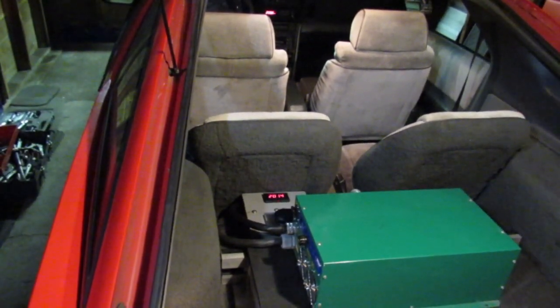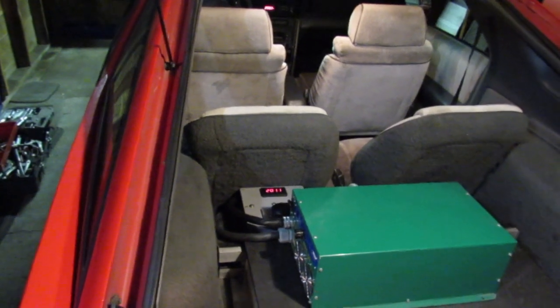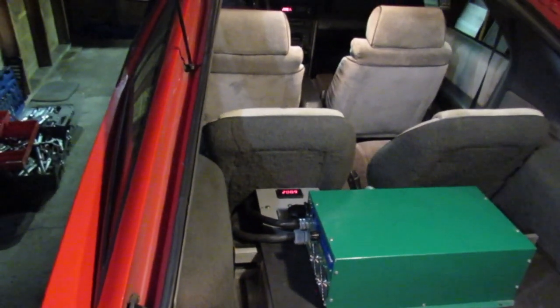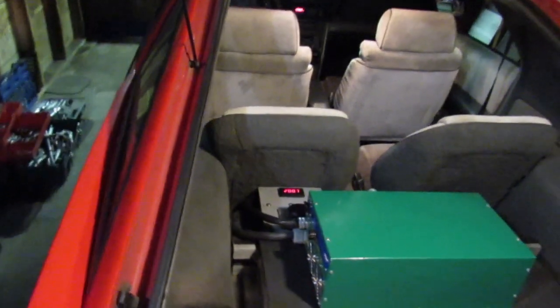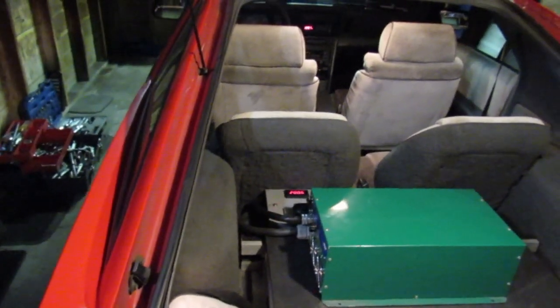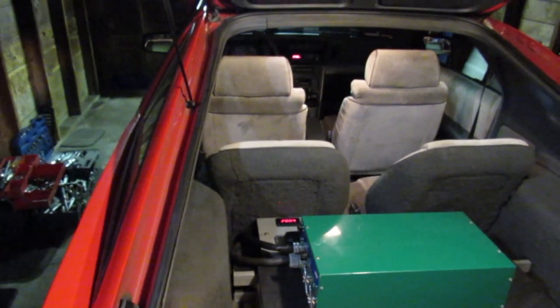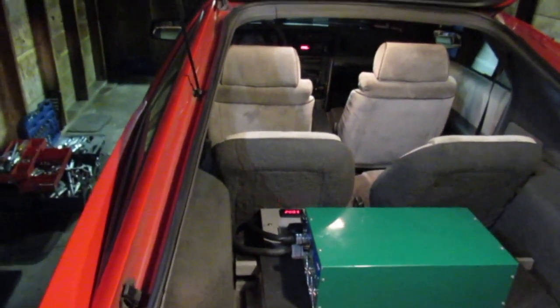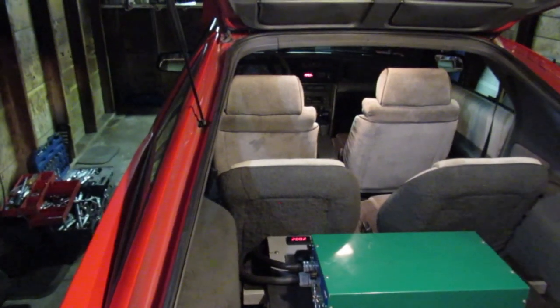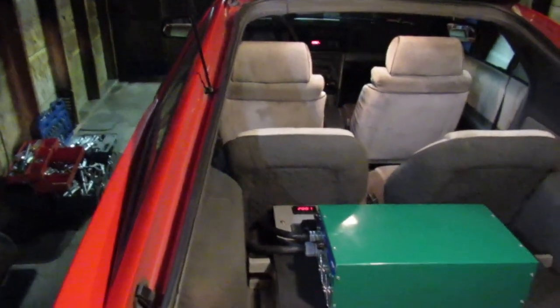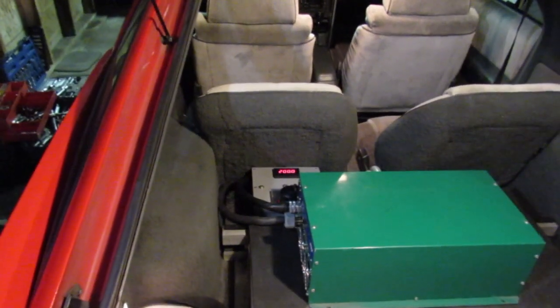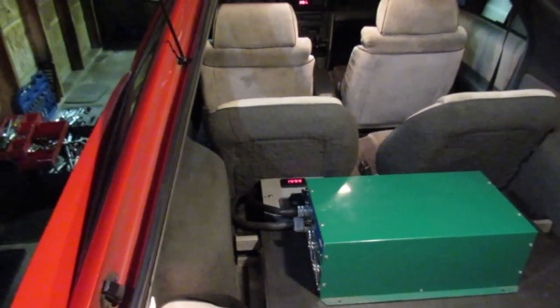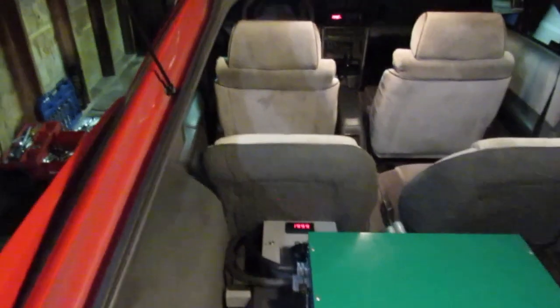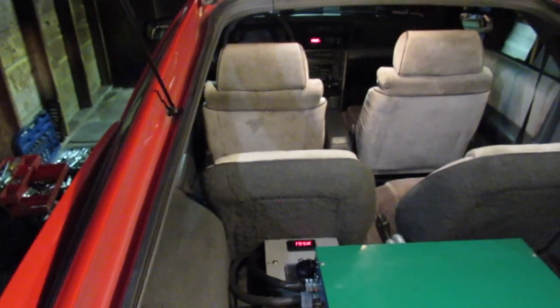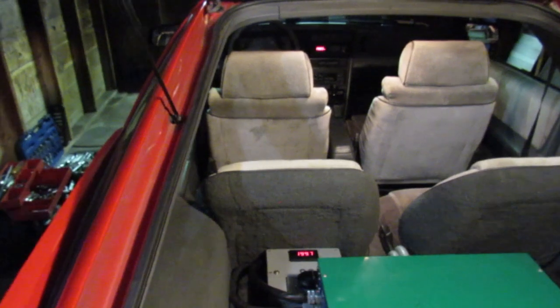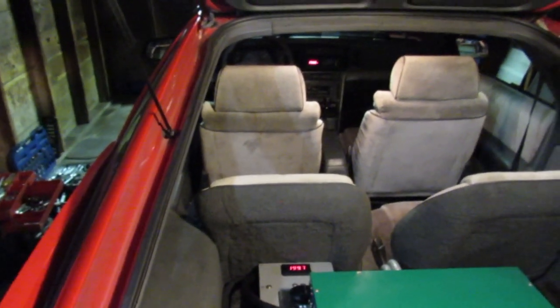It turned off, and the charger shut off, and now we're in that decreasing voltage for the battery settling phase. So once again, the JLD404 is showing 199.4, 199.3, whereas the charger buddy is showing 201, 200.1, 200.0, 199. So it's still showing higher than what the JLD404 shows, but again, I'm totally cool with that.